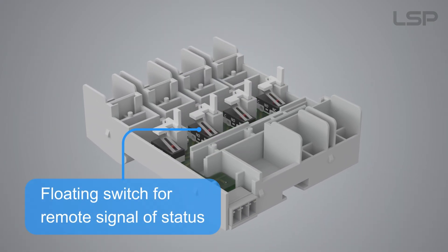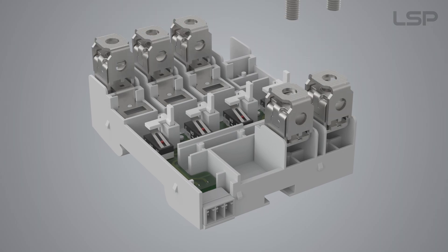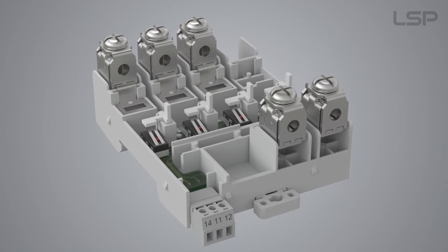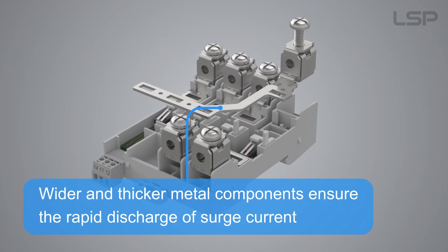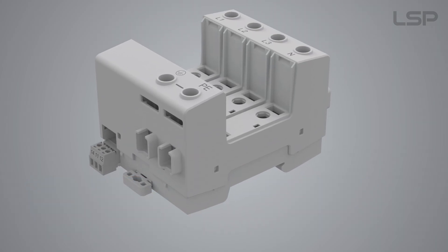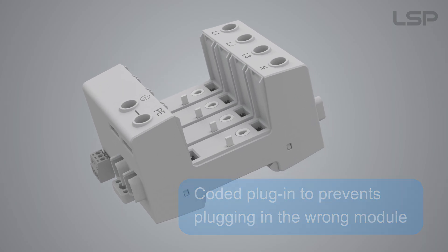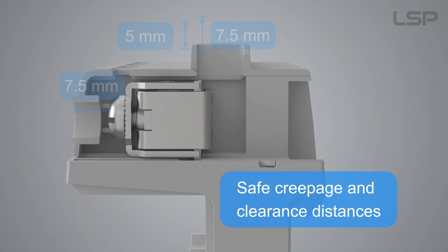Floating switch for remote signal of status. Wider and thicker metal components ensure the rapid discharge of surge current. Coded plug-in to prevent plugging in the wrong module. Safe creepage and clearance distances.